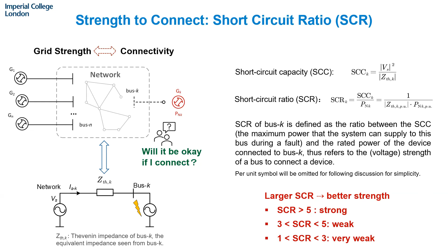Based on experience from engineers, when short circuit ratio is larger than 5, the system can be treated as strong. When it's larger than 3 but smaller than 5, it is weak. When it's between 1 and 3, it's considered very weak. And when it equals 1, it actually reaches the boundary of stability.